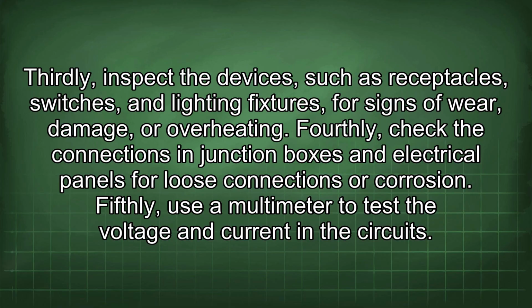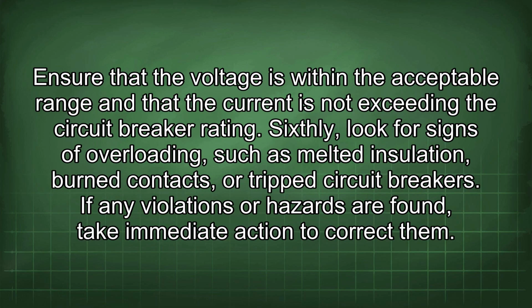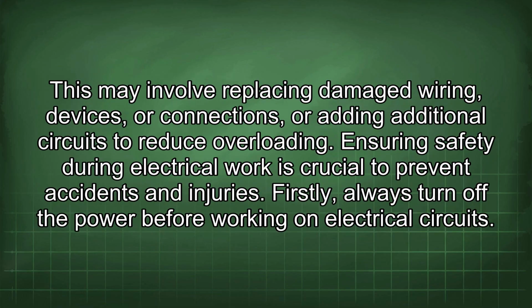Fourthly, check the connections in junction boxes and electrical panels for loose connections or corrosion. Fifthly, use a multimeter to test the voltage and current in the circuits. Ensure that the voltage is within the acceptable range and that the current is not exceeding the circuit breaker rating. Sixthly, look for signs of overloading, such as melted insulation, burned contacts, or tripped circuit breakers. If any violations or hazards are found, take immediate action to correct them. This may involve replacing damaged wiring, devices, or connections, or adding additional circuits to reduce overloading.